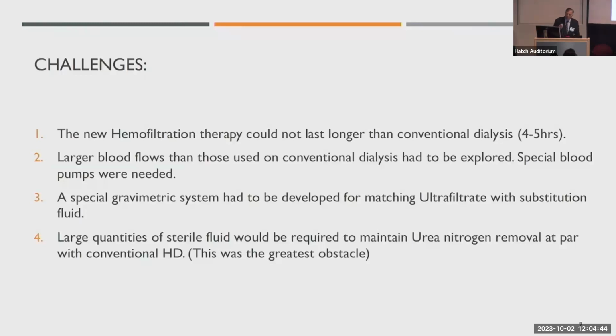Then we had to develop a system in which, as we are removing 100 mLs of ultrafiltrate per minute, we had to give 100 mLs or 90 mLs of substitution fluid. This balance had to be very careful. So we went to Italy, to a small town near Modena, where all dialysis was invented, and we found a person who built for us this special gravimetric system. In other words, a system that was able to replace the fluid that we were taking out with infusing fluid. But the largest problem we had was that we would need extraordinary quantities of fluid.